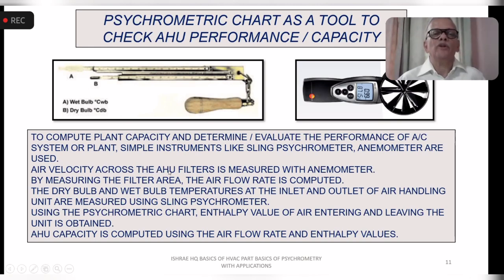Air velocity across the air handling unit filters is measured with the anemometer. Then you have the square feet or square meter area of the filter, and then you can calculate the air flow rate. The dry bulb temperature and wet bulb temperature at the inlet and outlet of the air handling unit will be measured using this sling psychrometer. And then by using the psychrometric chart, you will find the enthalpy values of air entering and air leaving. And then you have the AHU capacity, which can be computed using the air flow rate and the enthalpy values, because that is the data required to calculate. So you have a very simple set of instruments and you can calculate the capacity or check the performance against your design parameters.